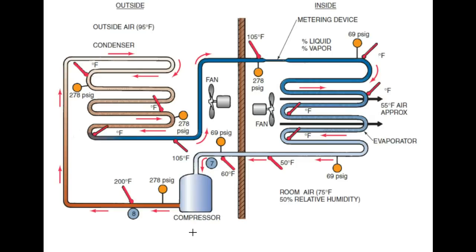So we have an undercharged system. There's not enough refrigerant. We still have this solid column of refrigerant coming into the fixed orifice, and it flashes over to saturated refrigerant. And it is changing state and absorbing heat, just as it was designed to do, and it's pulling out heat from the indoor air. And it's going to do so, but at a certain point, not at the design point, but because we're undercharged, we now have boiled off all the refrigerant. It's changed its state completely from liquid to vapor earlier on in the coil than it should be.